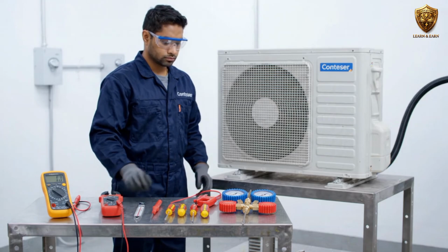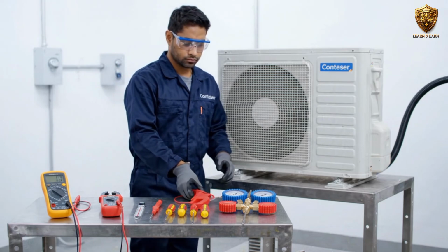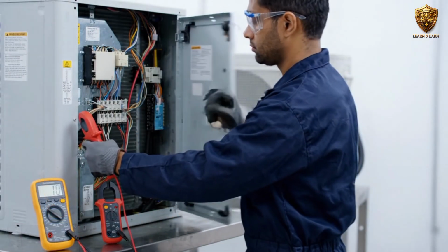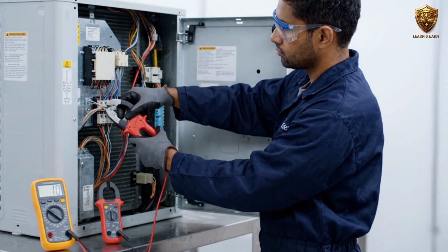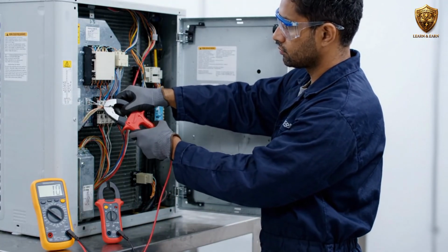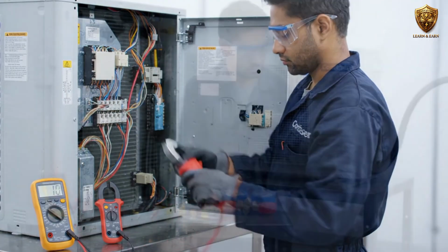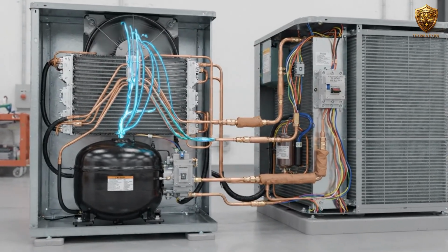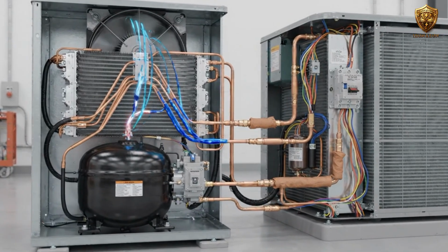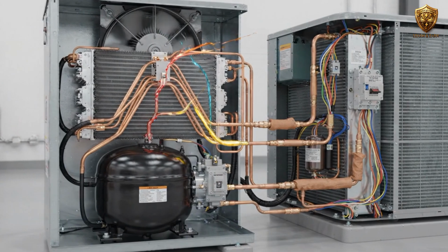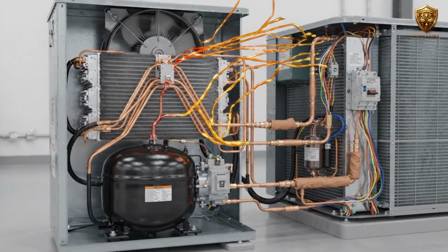It could be poor airflow, a dirty filter, a frozen evaporator coil, a failed capacitor, a bad contactor, a weak compressor, low refrigerant caused by a leak, or even a simple power or control problem. That is why troubleshooting is a skill, not just a list of repairs. In this training, we will follow the way a technician should think when a cooling system is not performing correctly. We will start with the simple checks and then move toward electrical, airflow, refrigeration, and compressor problems.